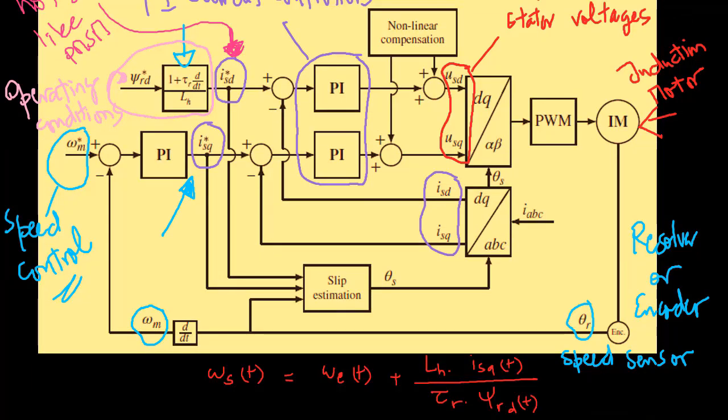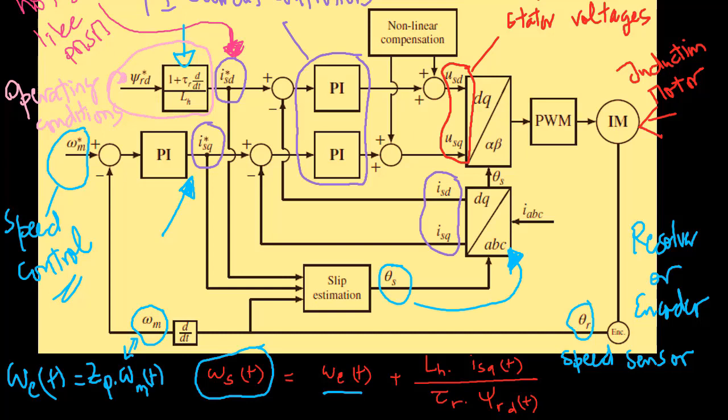Beyond that, ωs is not measured directly but is used in Park transformations to convert voltages and currents variables in the reference frame αβ to reference frame dq. Thus, the estimation of ωs is required as part of the control systems, and this is called the slip estimation.